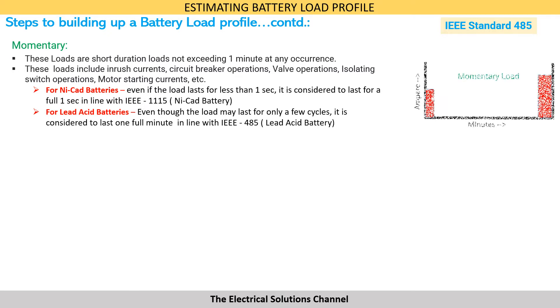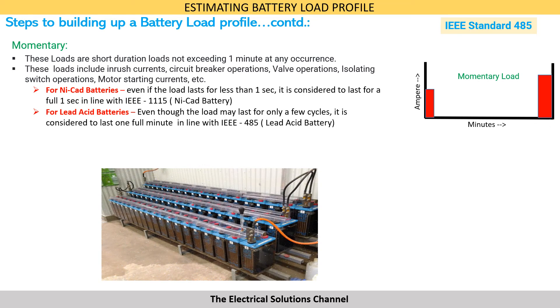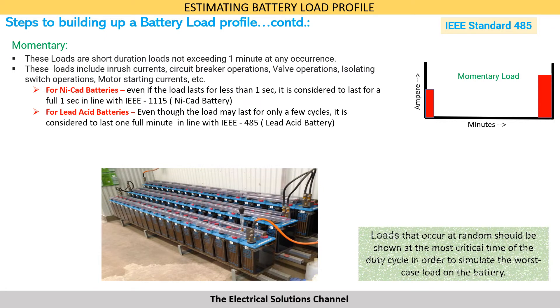For nickel cadmium batteries, even if the load lasts less than one second, it is considered to last a full one second, in line with IEEE 1115. For lead acid batteries, even though the load may last only a few cycles, it is considered to last one full minute, in line with IEEE 485. Loads that occur at random should be shown at the most critical time of the duty cycle in order to simulate the worst case load on the battery.